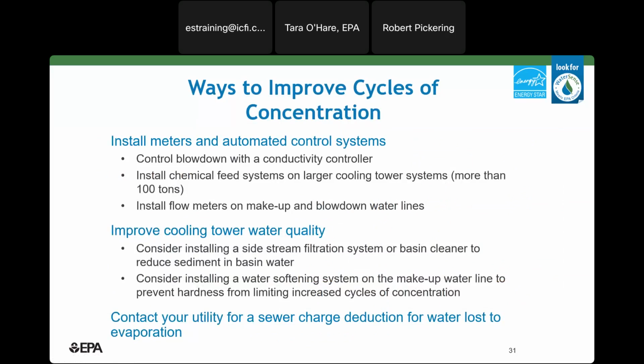I mentioned this earlier, but one important cost-saving measure is that with appropriate sub-metering, some utilities will let you deduct the quantity of water you evaporate from your sewer bill. So these savings can be quite significant because cooling towers are big water users. The cost savings from a sewer deduction can often be used to offset the upfront costs of installing meters or other control mechanisms.